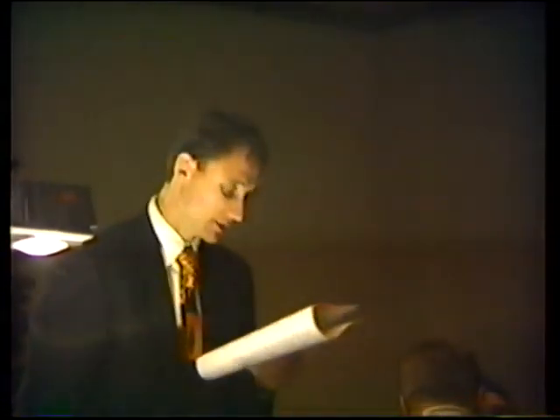Now, in order to demonstrate that you can meet those, some of that technology I just started showing you is needed to quantify that. There's no way you're going to be able to do that unless you have some engineering basis to do it. The flashover criteria. There is a clinical definition of flashover. Basically it's defined as that the upper layer temperature, basically above the smoke layer that's descending, will not exceed 1,100 degrees Fahrenheit, and there won't be a radiant heat flux at the floor of 20 kilowatts per square meter. That's a clinical definition of flashover.